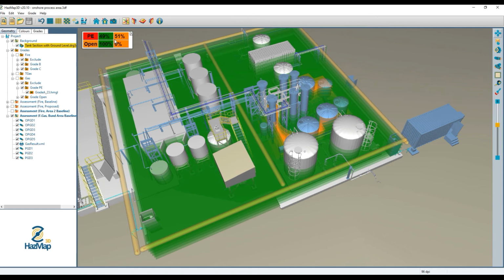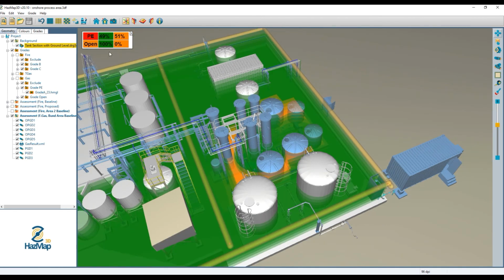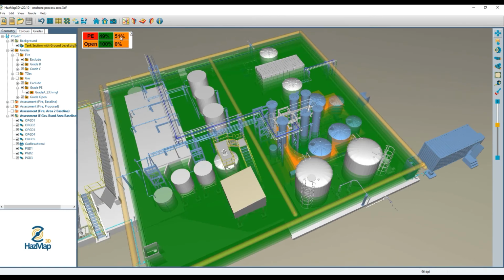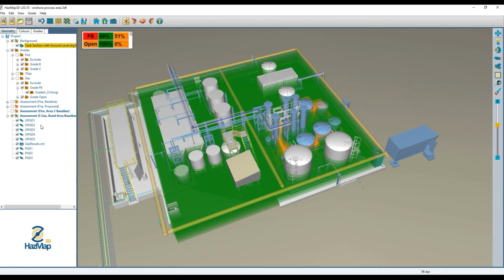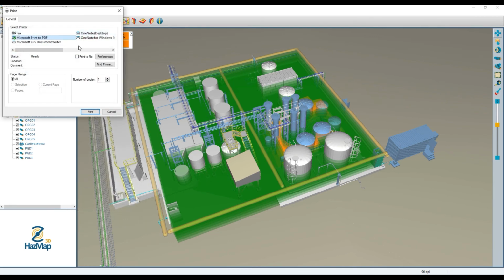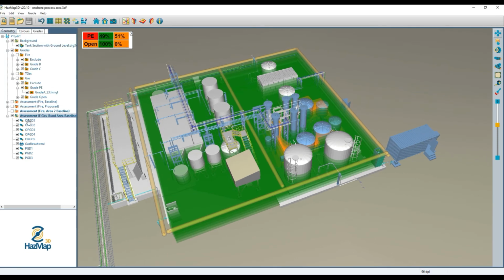The PE coverage might seem a little bit low for 2 out of N, but again, it's just a whole lot of narrow gap spaces between areas of good coverage. So even though that number might not look great, I'm pretty happy with it, especially considering I've got at least 1 out of N low voted coverage everywhere. And so with that done, I can say print report, tell it what I want, and output to a PDF, and then I'm going to be done. Just as some cleaning up stuff I can do.